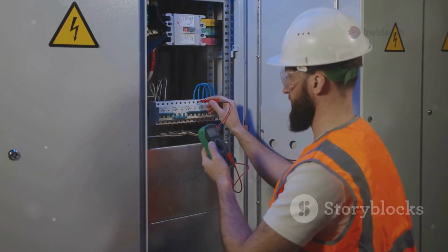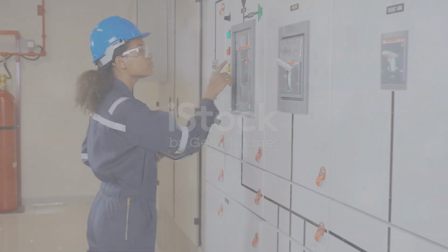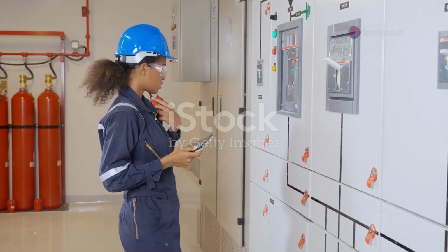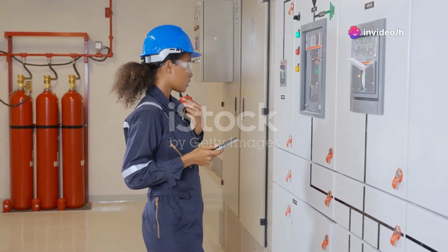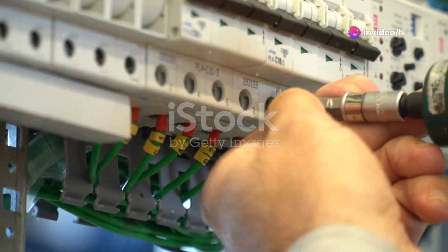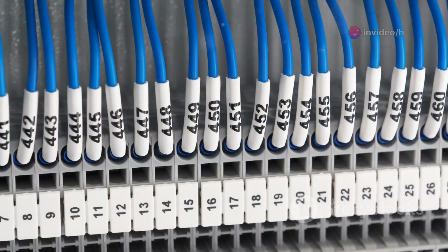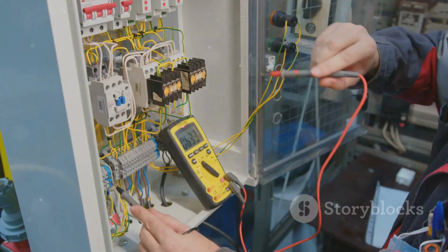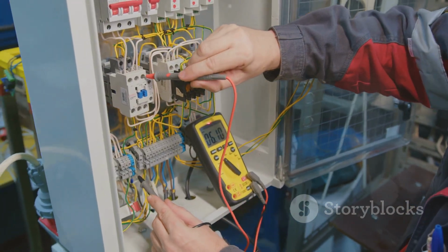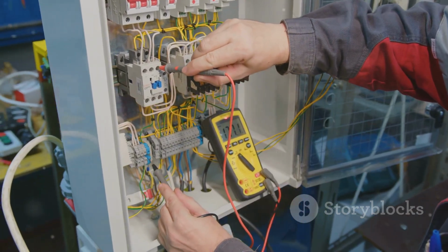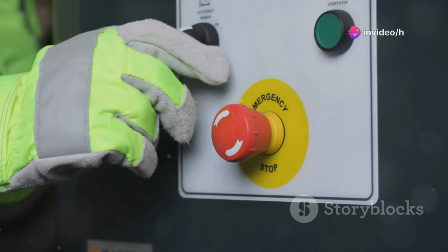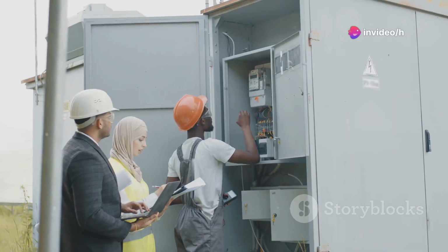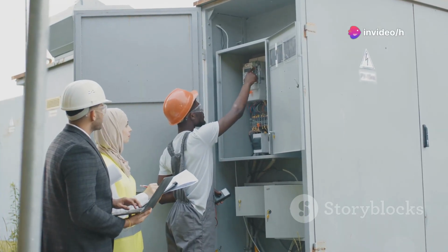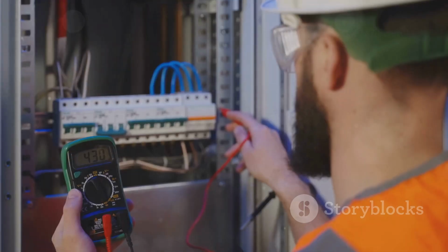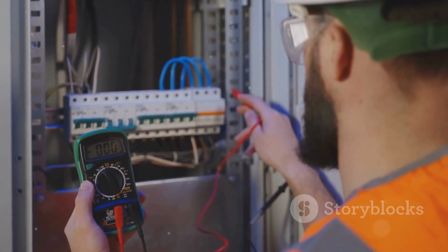Final step: inspection and testing. Let's finish strong. Assembly's done, but the real test is inspection and power up. Check every terminal and connection for tightness. Confirm all labels are clear and accurate. Use a multimeter to check for shorts and continuity before energizing. Test the emergency switch and alarm relay manually. Power up the main RCCB first, then each motor circuit one by one. Check voltages, motor rotation, and running current.